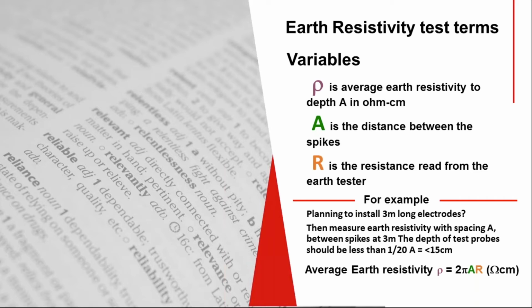Another thing to mention is that 1/20th you see there. If you were strictly following the Wenner method, it requests that you drive the probes in 1/20th of the distance that they're horizontally spaced, and you'll see that in the literature a lot. It's not that critical, from conversations I've had with testing services. So if you're trying to measure a shallow depth and you're trying to put your probes in at 1/20th and they barely hold, don't worry about it. Just drive them in enough to get a measurement. There'll be some error introduced, but it's typically not critical. Don't base the whole success of your method on using exactly a 1/20th depth on your probes.